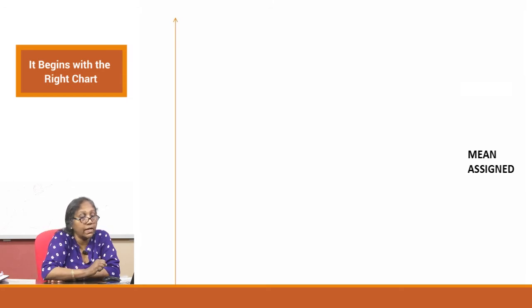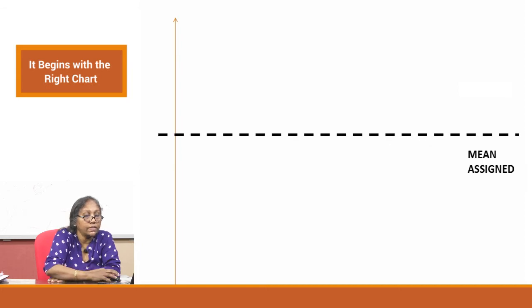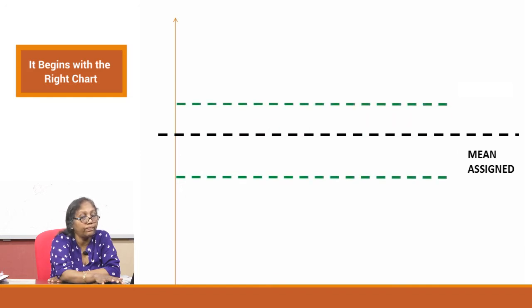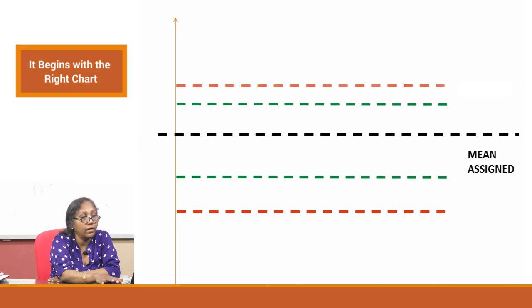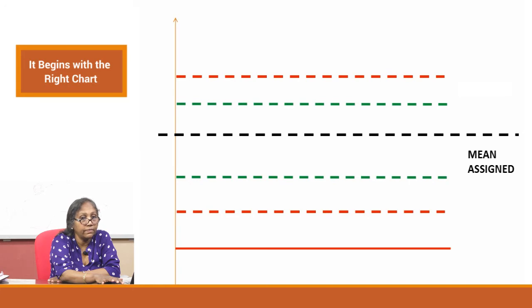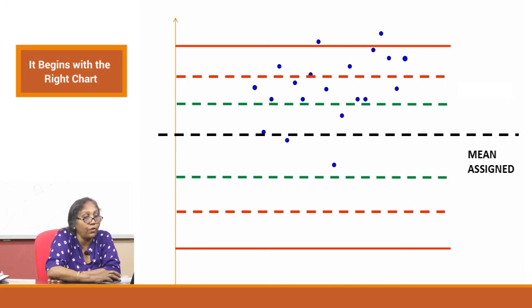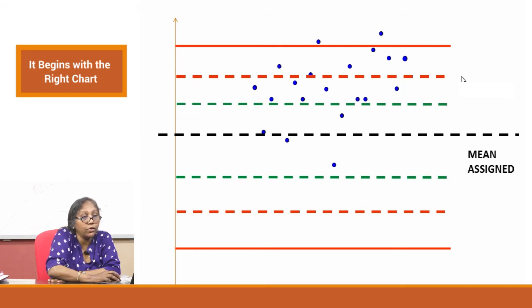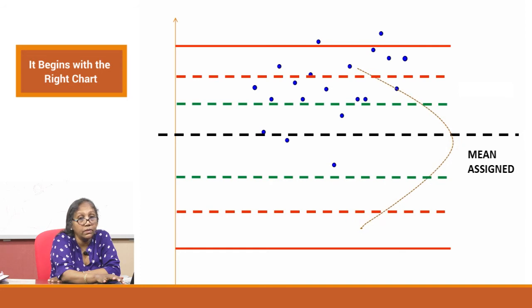Looking at this slide: this is a control we are running. Your assigned mean is here, with minus 1 SD, plus 1 SD, minus 2 SD, plus 2 SD, minus 3 SD, and plus 3 SD. Over 20 or so analyses, your data points are falling here. You have your assigned mean here, but the actually observed mean is somewhere else — there is an anomaly. The Gaussian you are expecting is here, but the Gaussian that is developing is there.